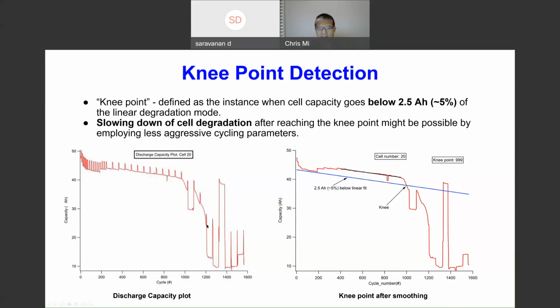As you can see here, we look at the capacity degradation and come up with algorithms to identify the aging knee. We look at the blue curve here. As you can see, the blue curve is basically away from the actual SOH, but once they cross the blue curve, we think this battery has reached its aging knee. That's how we can identify it.